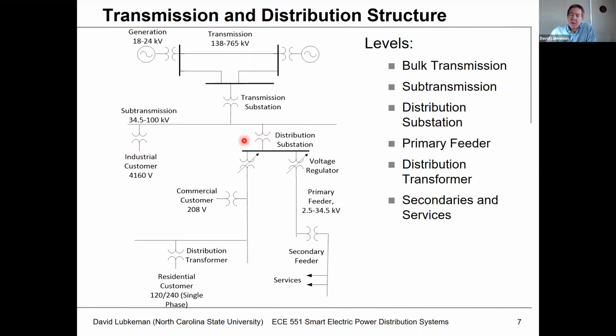When we get closer to the customers, we have a distribution substation, which steps it down to the medium voltage, typically between 2.5 and 34.5 kilovolts line-to-line in the United States. There's no US standard for this; it's based on history and what utilities started building probably 100 years ago, and they've simply kept their voltages.